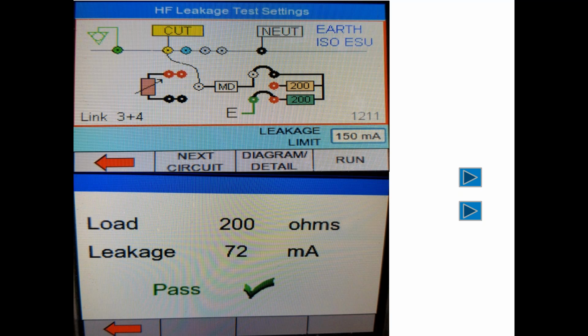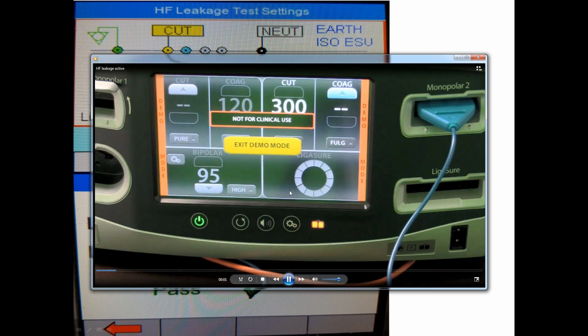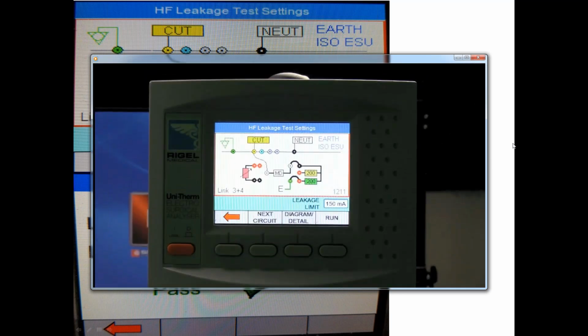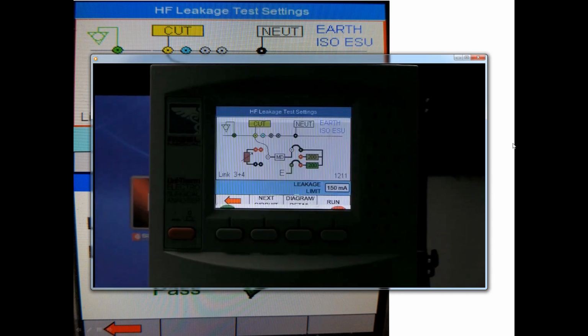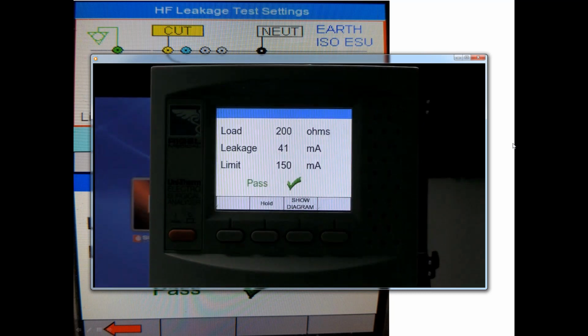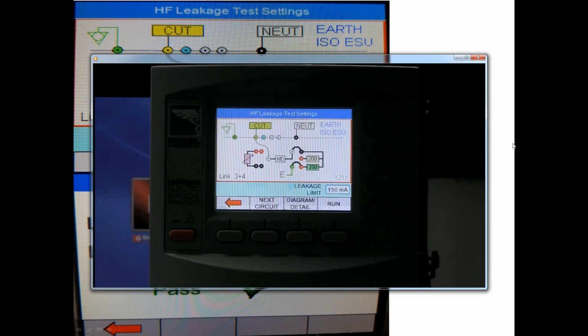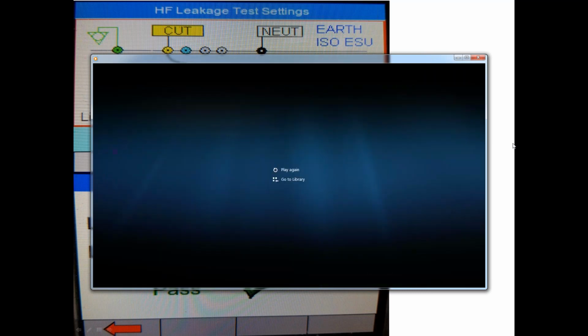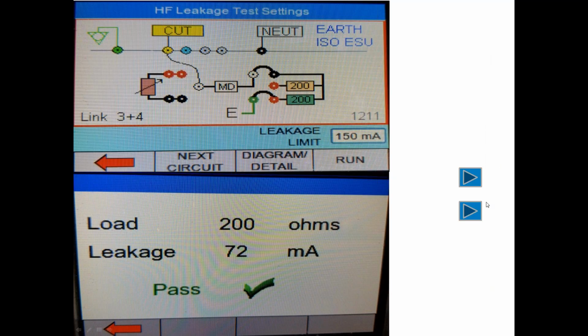So I'm going to show you two different tests here. We're going to do the active electrode first. So from the active electrode, there's your test screen that shows you what the limit was and what the actual measured value is. Now, in the data that we save internally, we would only show you the test results, not the limit, as that would be part of the test procedure. So that was the active electrode.